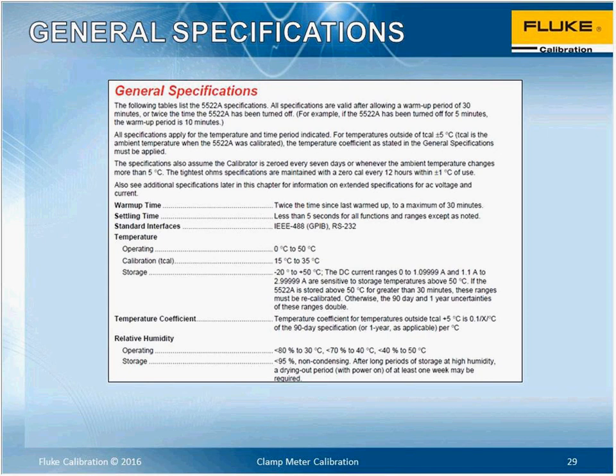Also, the operating temperature is very important. In many labs it's controlled, but once you start thinking about taking it out to an on-site calibration lab that you would set up, that's where operating temperature becomes very important. So make sure that if you took it into a machine shop or a process lab without environmental control, you still have the ability to produce the results you would in a controlled lab.